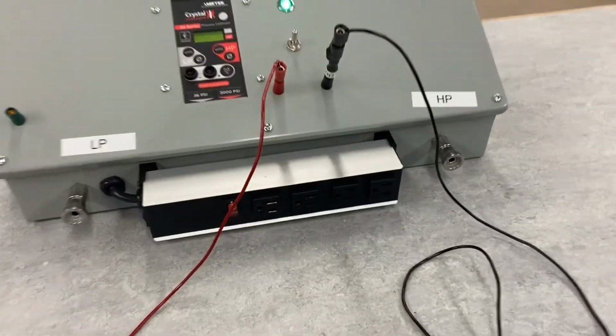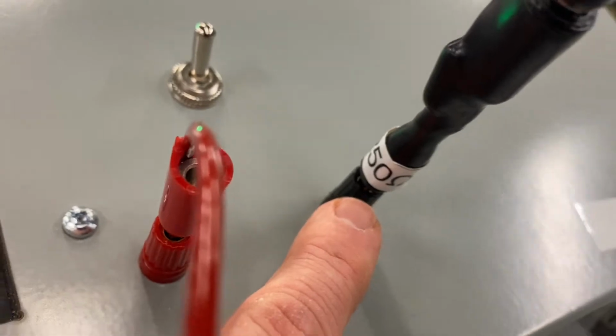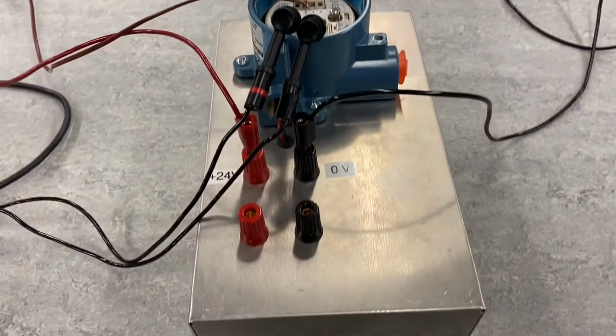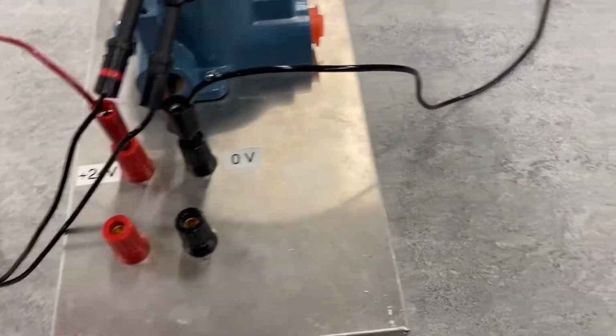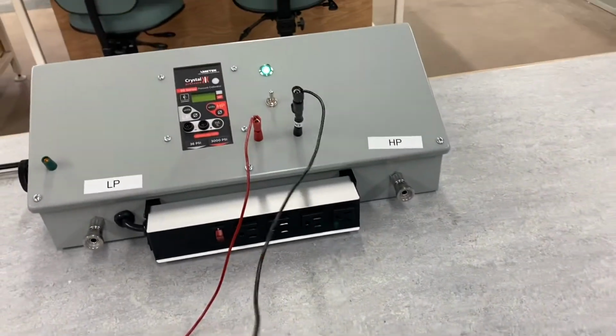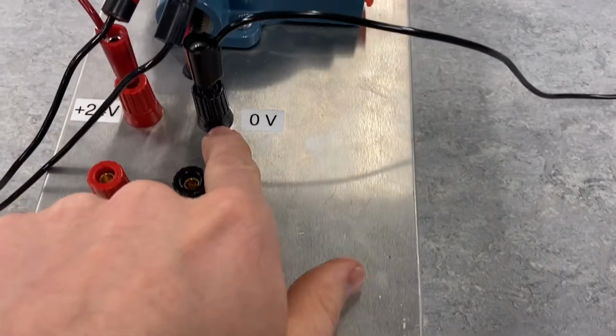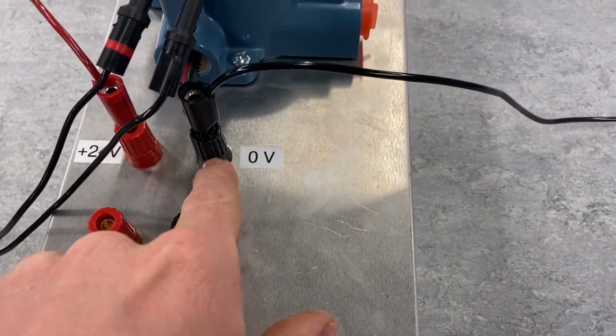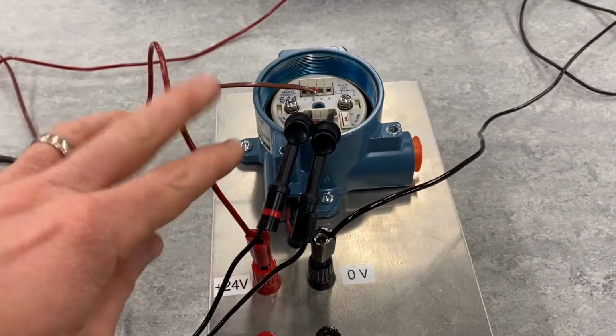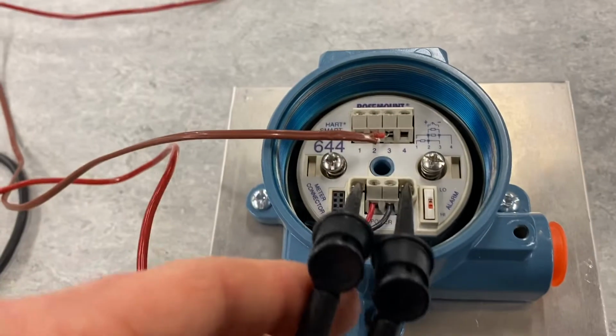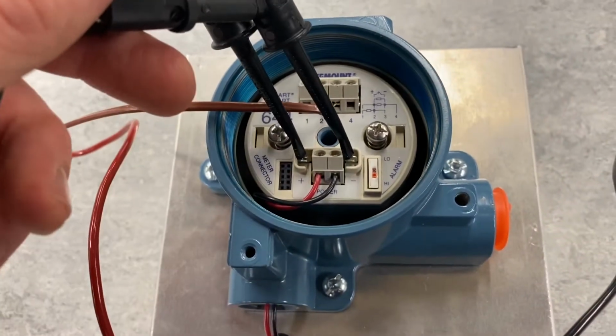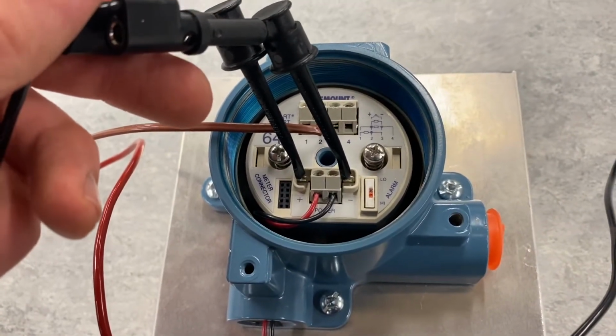We have a 250 ohm resistor here connected in series with our power supply, which runs down to our 24 volts right here, and then our 0 volts, or sorry, not 0 volts, it should be negative, I guess, negative 24 volt back over to our power supply there. So we've got a loop connected there. We've also got our Trex communicator here. This is to communicate with the smart device so we can make changes to it.